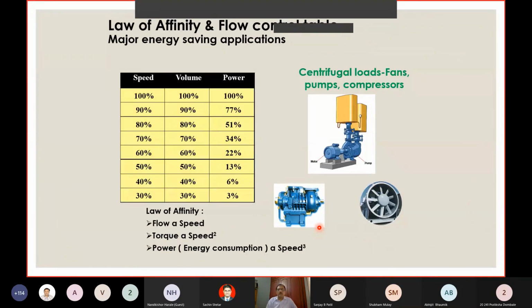So while talking about the pumps, the law of affinity also has to be understood. Only one slide, and I want you to understand this. For pumps, fans and centrifugal compressors, which are called variable torque loads, a VFD is an excellent choice for energy saving compared to other means of reducing flow.